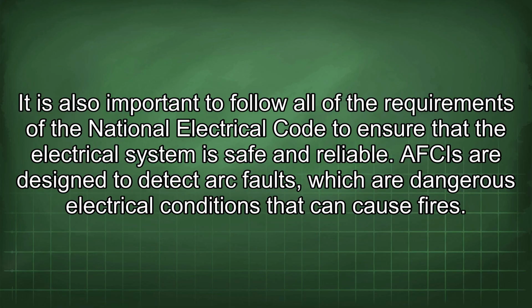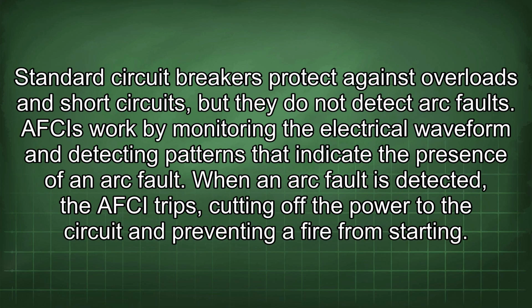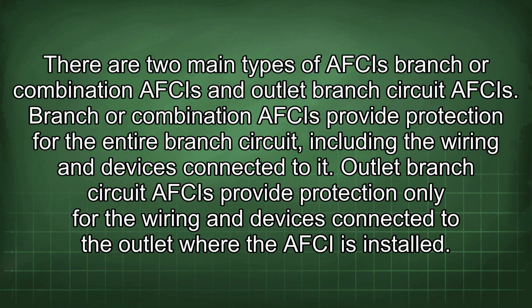AFCIs are designed to detect arc faults, which are dangerous electrical conditions that can cause fires. Standard circuit breakers protect against overloads and short circuits, but they do not detect arc faults. AFCIs work by monitoring the electrical waveform and detecting patterns that indicate the presence of an arc fault. When an arc fault is detected, the AFCI trips, cutting off power to the circuit and preventing a fire from starting. There are two main types of AFCIs: branch or combination AFCIs and outlet branch circuit AFCIs.